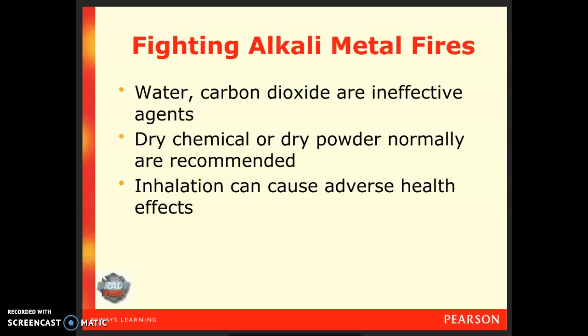If you encounter an alkali metal fire, sodium, potassium, or the like, water and carbon dioxide are obviously going to be ineffective here. Water, because water reacts with the metal itself. Carbon dioxide does not pull away nearly enough heat to suffocate the flame itself. Usually with metal samples that are finer, a carbon dioxide extinguisher will actually push the fine powders away, which will only help to spread the fire instead of put it out.